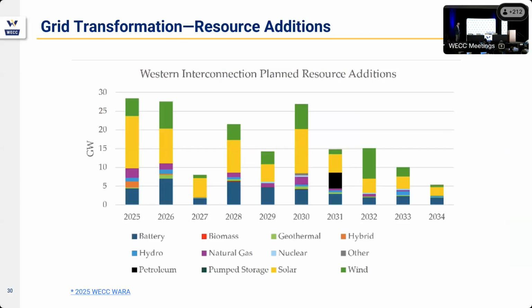This is also out of our loads and resources data that we collect every year. This is the additions that we're expecting to see in the Western Interconnection over approximately the next 10 years. If you notice, it's very highly dependent upon solar and wind, a little bit of battery, not a lot of anything else of anything substantial. So most of our new resource additions, the vast majority, are going to be IBR related, with zero inertia. One of the things that's really interesting about knowing what the inertia is, it tells you a lot about how the transmission planning models respond when you're doing transmission planning studies. Loss of large load, all the things that we're really interested in.